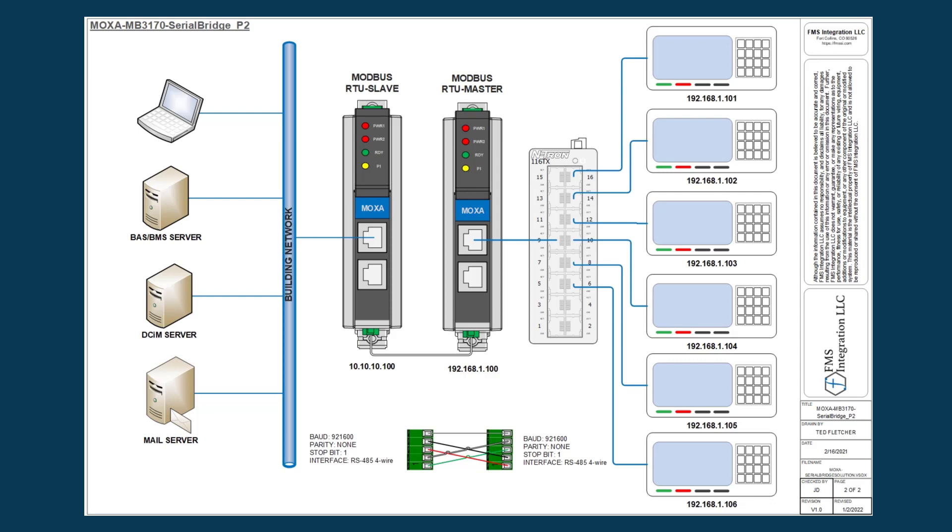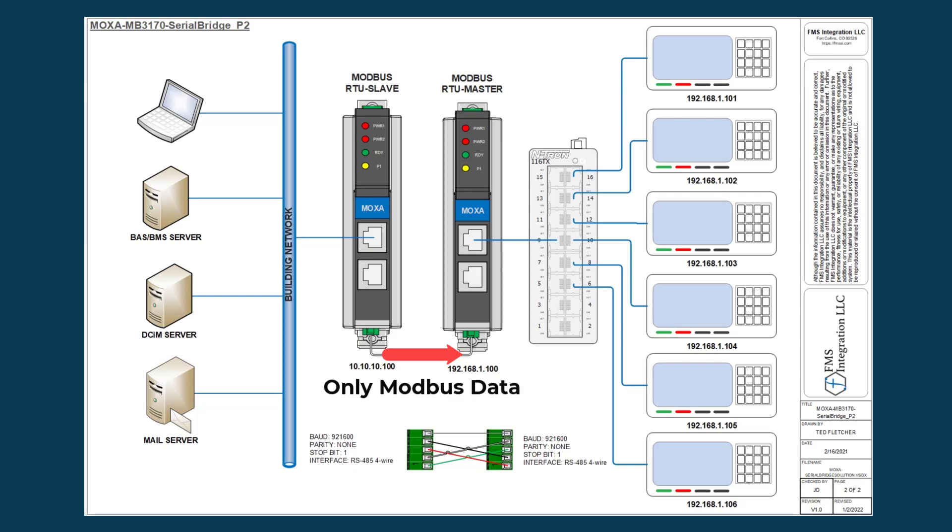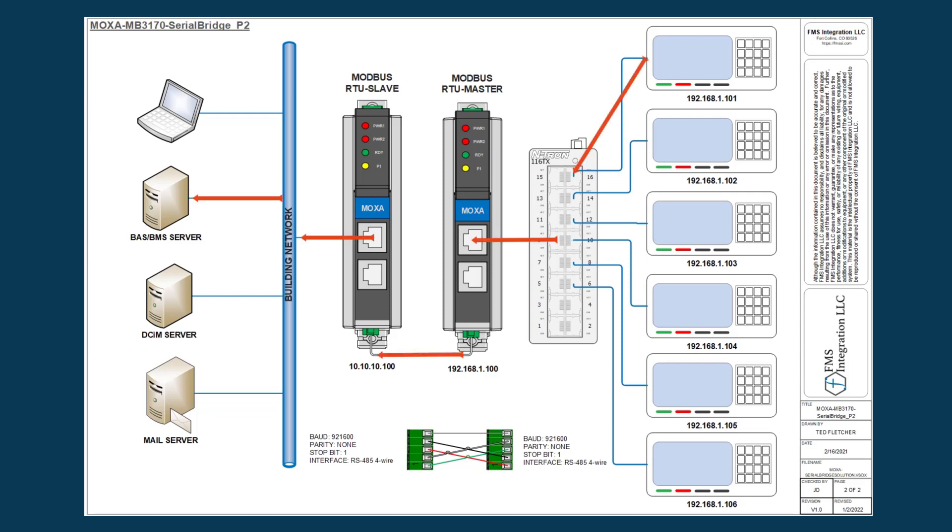With a Moxa bridge solution, the master device sends a request. The slave Moxa receives the request. The request is then converted to Modbus RTU and sent over the serial cable connecting the two Moxa devices. Only Modbus data is able to be requested and sent over the line. The master Moxa routes the slave ID being requested to the correct IP Ethernet device. Once received, the packet request is sent back to the original system requesting the data.